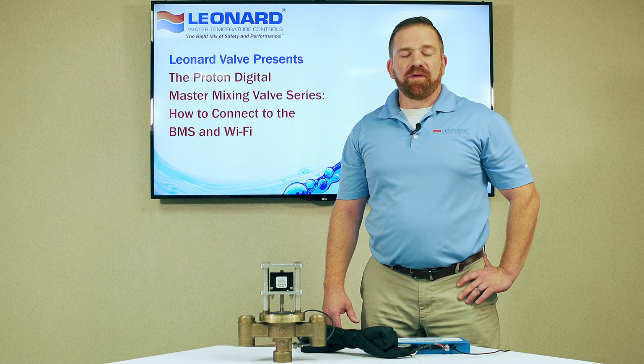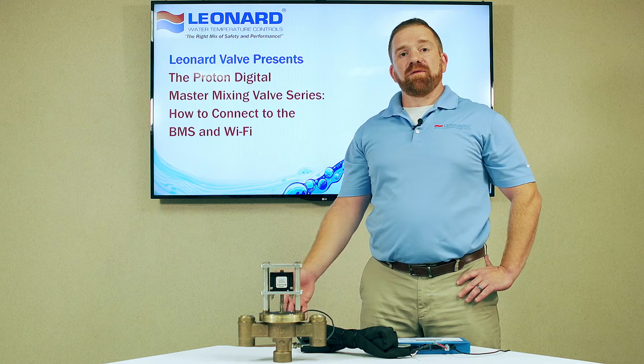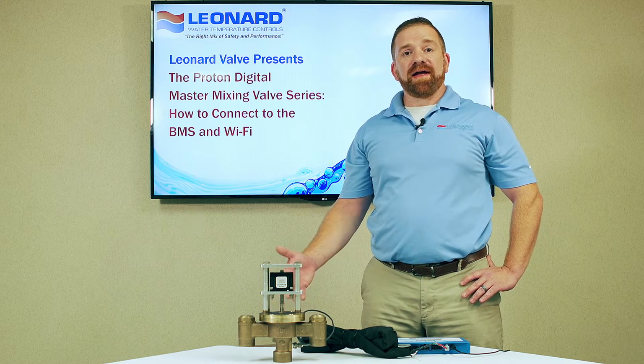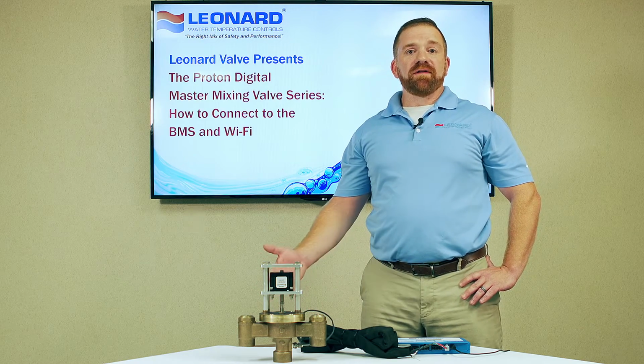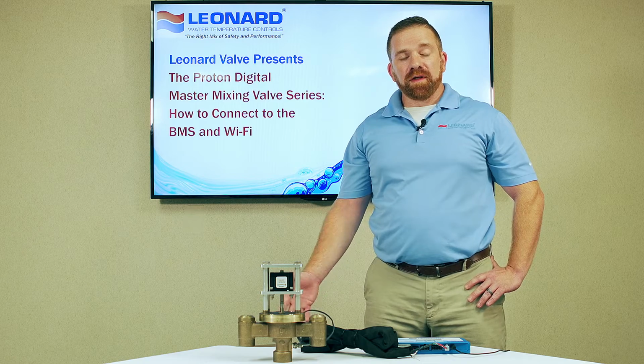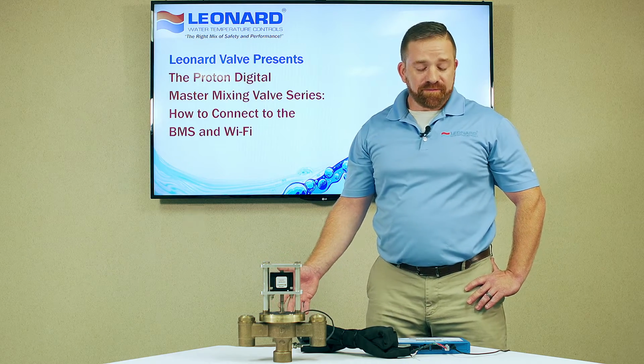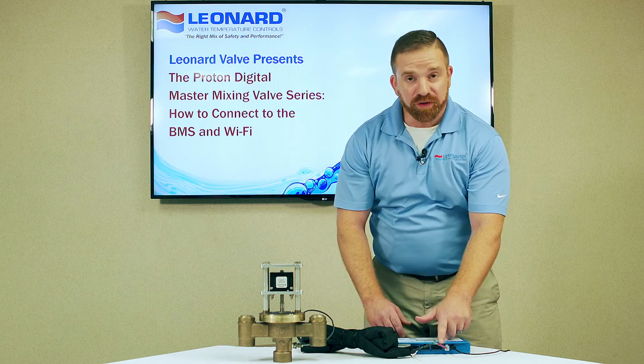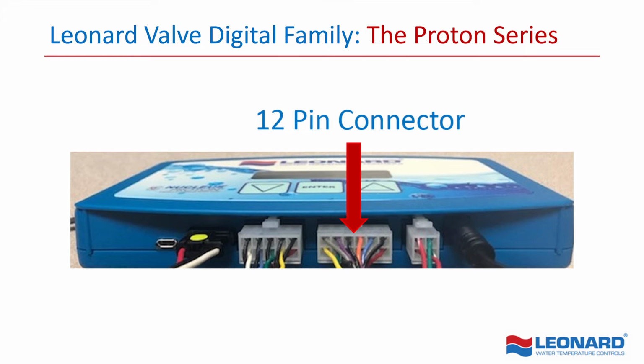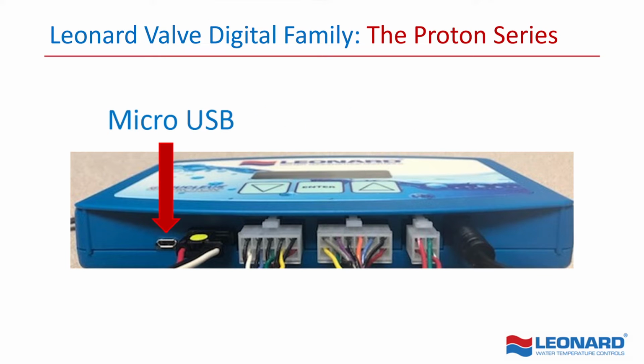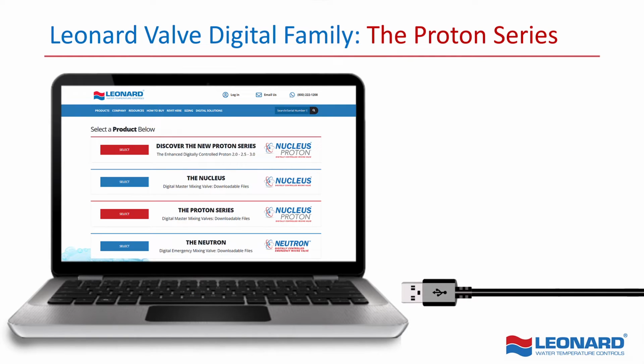I'm going to go into the process of both how to set up your Proton 2.5 to BACnet or Modbus, or your Proton 3.0 to Wi-Fi. First, we'll start with the 2.5. So you want to make sure you have that 12-pin connector plugged in, and on the correct terminals, 1, 2, and 3, you also want those already wired to your BMS system. Plug in a micro USB to the left side of this controller, and on the other end, you want to plug it into your laptop.